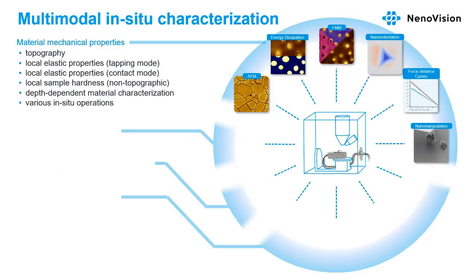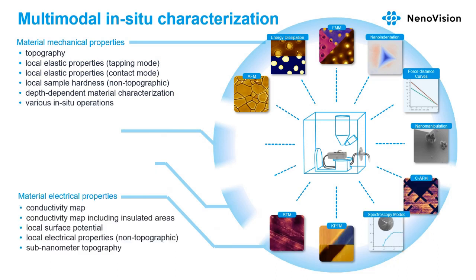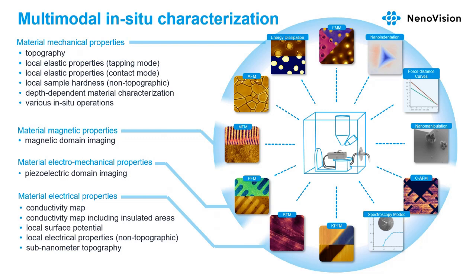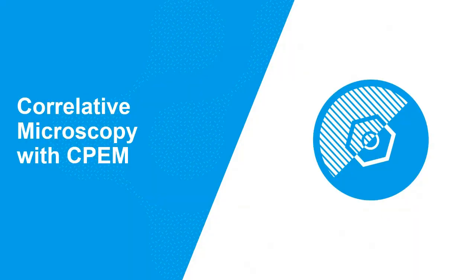With LiteScope we measure several techniques. For mechanical properties: topography, energy dissipation, nano indentation, and measurement of local elastical properties. For electrical properties: conductivity mapping, local surface potential, I-V curves, and so on at high resolution. We can also measure piezoelectric domains and magnetic domain imaging — all within the SEM.